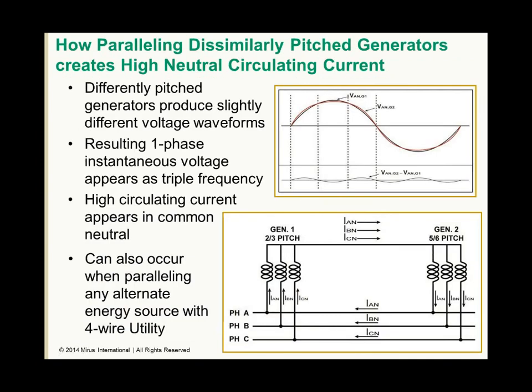The reason high neutral circulating currents appear when paralleling generators with different pitches, or paralleling alternative energy sources with a 4-wire utility, is that the voltage waveforms can be slightly different even when RMS voltages are perfectly matched. So that's shown here on these waveforms. You can see the blue has got a higher peak value than the red. The red has got wider shoulders, and that's the typical difference between two different pitches of generators. One might be a 2/3 pitch generator and the other a 5/6 pitch generator.